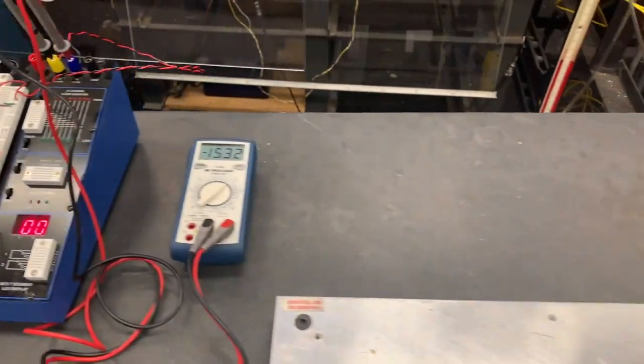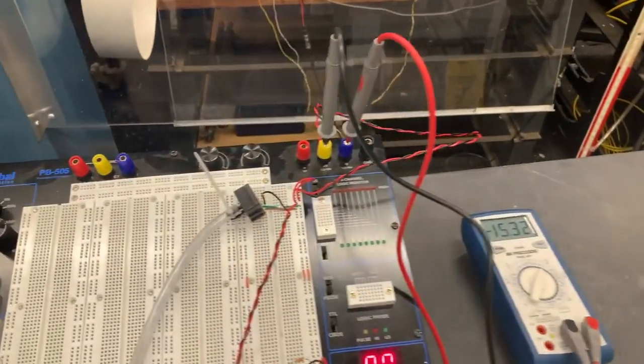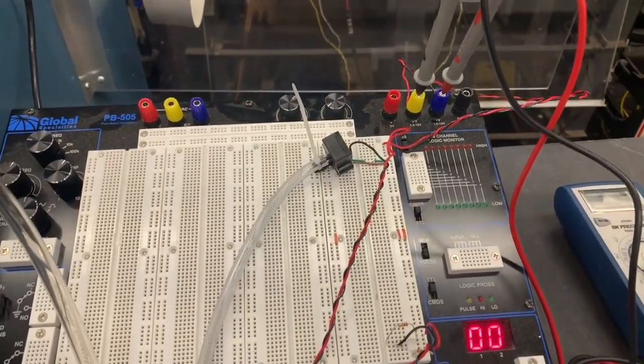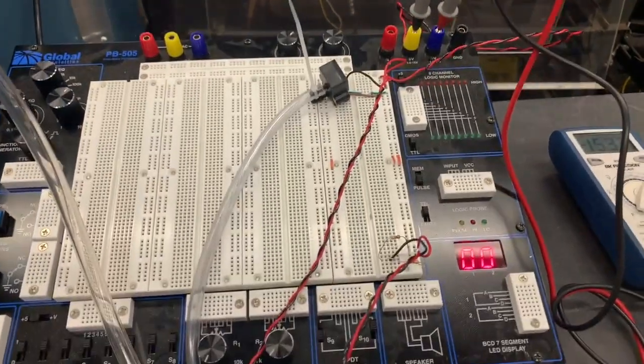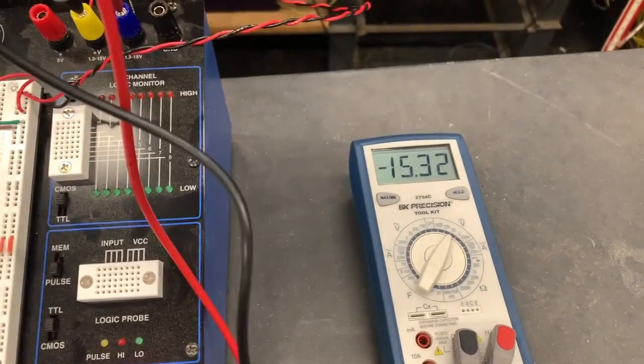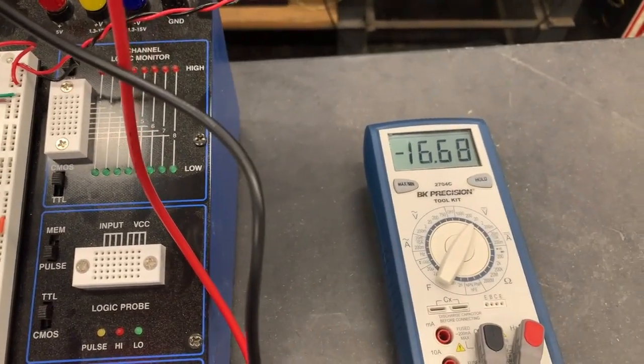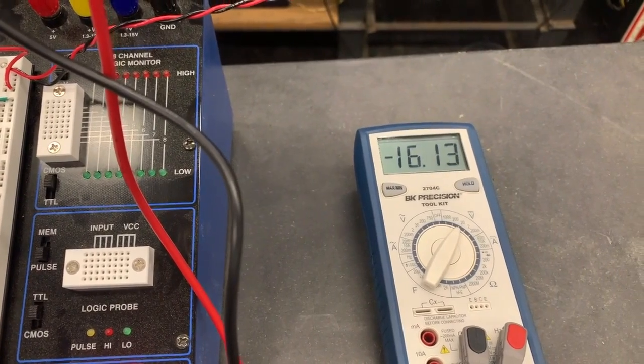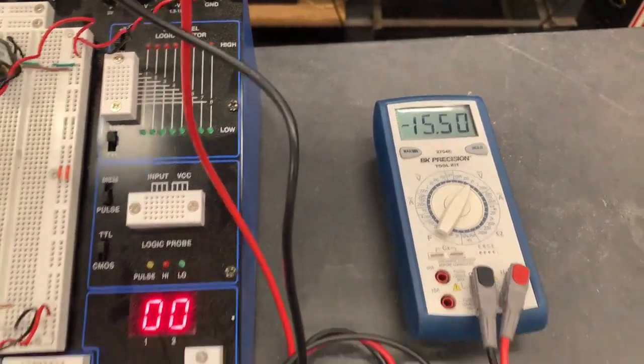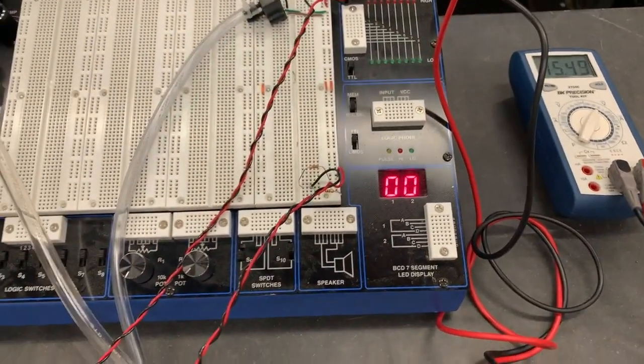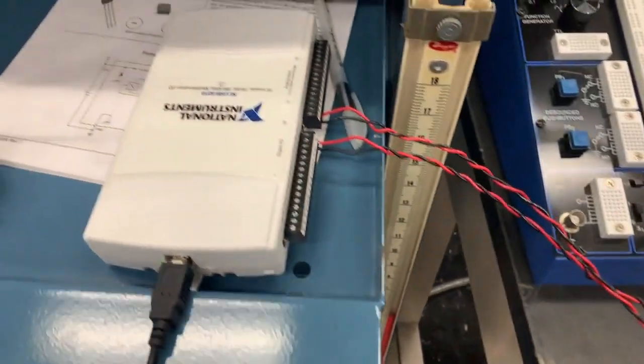I noticed when supplying this with the quoted 8-volt excitation, because there's not a particularly large pressure difference provided by this jet, the output was incredibly small. So I chose to increase the excitation voltage to around 16 volts or just below. This meant I was effectively doubling the output, making the device twice as sensitive and giving twice the precision in my results.